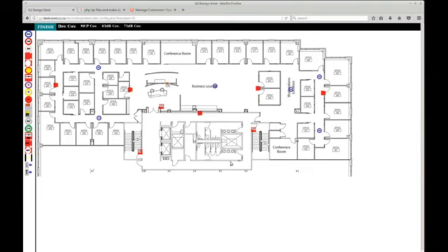Okay, we can now have a look at our coverage by selecting the detector coverage. Using our 10 meter scale, it automatically calculates where it thinks our detectors are covering based on a smoke detector's coverage pattern. We can now click and fill in the few gaps on the corridors because we're trying to do protection on the corridors of this building whilst our coverage pattern is switched on.